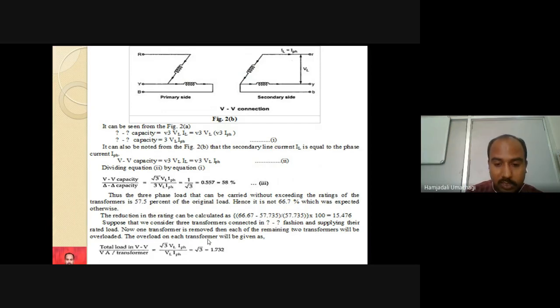The overload on each transformer will be given as, so how much overload is it going to carry? Suppose the first system is delta-delta, then each of the transformers will carry 100% of the load. But now one transformer is out of service, so the work carried by that out of service transformer will be taken care of by the other 2 transformers. Due to that, the other 2 transformers will get overloaded. So what is the overloading that is experienced by each transformer, that we will see here.